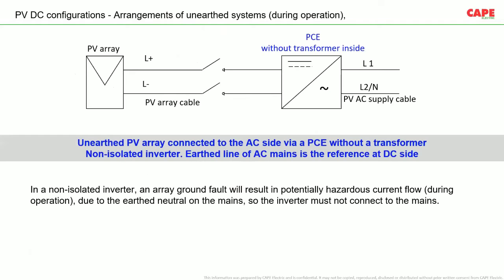Say, for example, this is an unearthed system. PV DC configuration, arrangement of an unearthed system. What is unearthed? The DC side is unearthed. The positive and negative are completely double insulated. It is connected to the PCE without a transformer inside, and the PCE is connected to the incoming power supply, the phase and the neutral power supply.